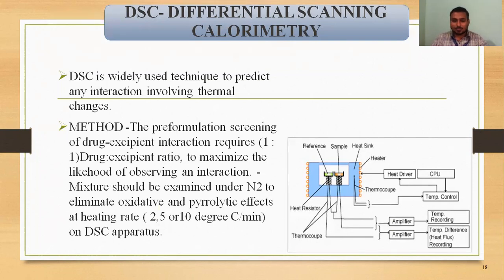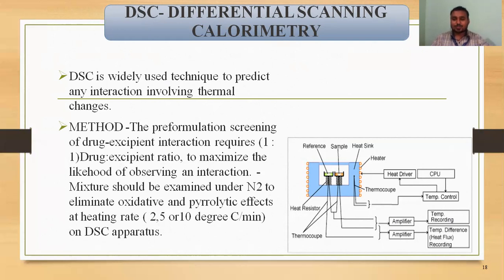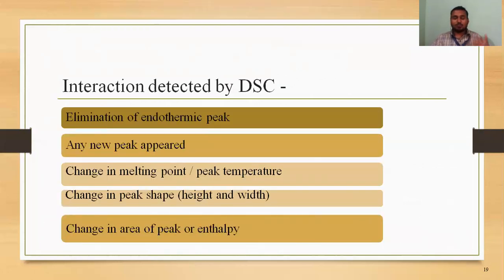The DSC apparatus has two holders: one sample holder and one reference holder. Inside, a heater is fitted along with a heat sink. A CPU is connected with the DSC apparatus; two amplifiers are also required along with heat resistors and thermocouples. One software and a computer are required for calculating and storing the data. The main factor recorded is temperature.